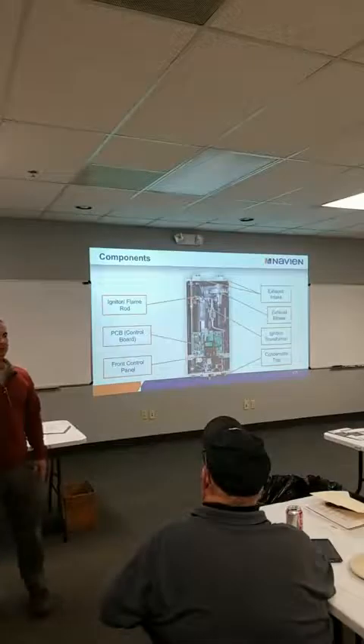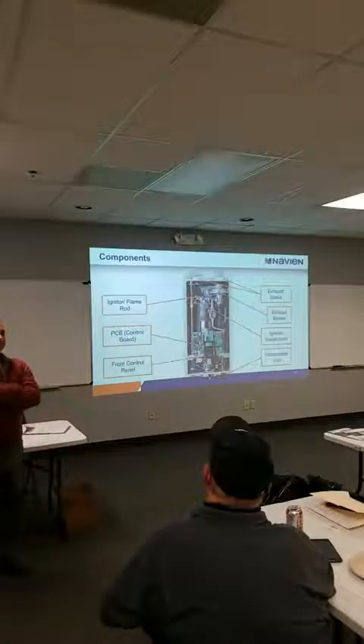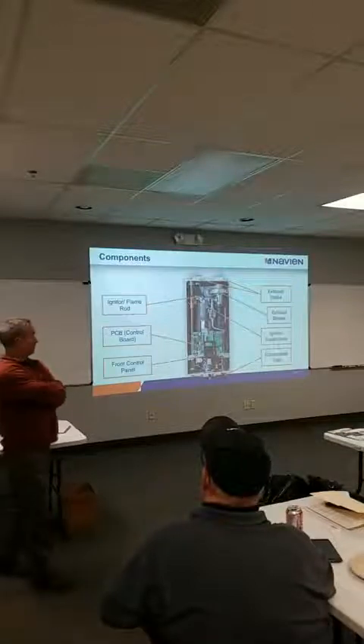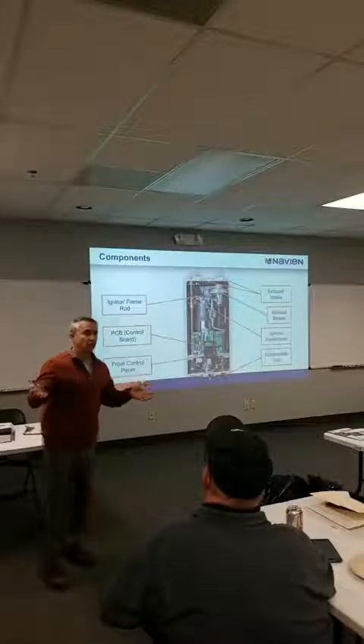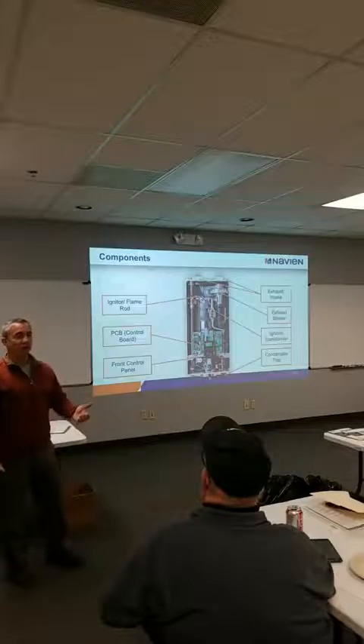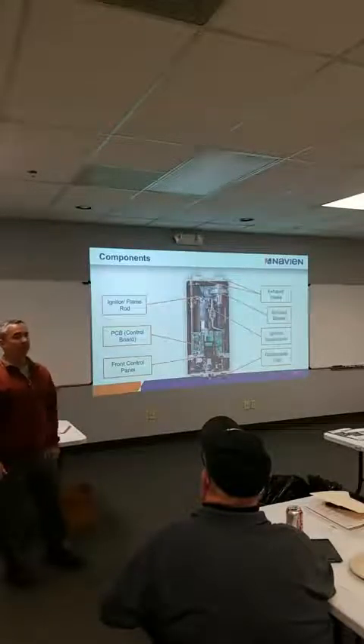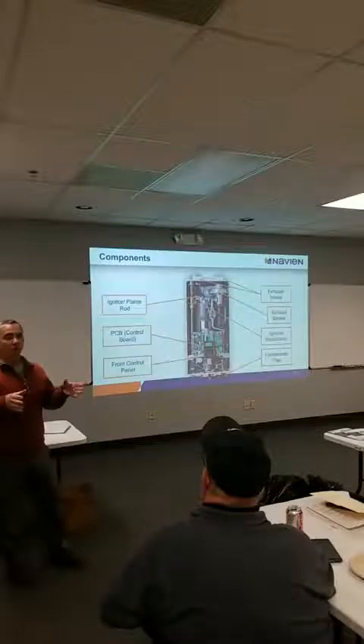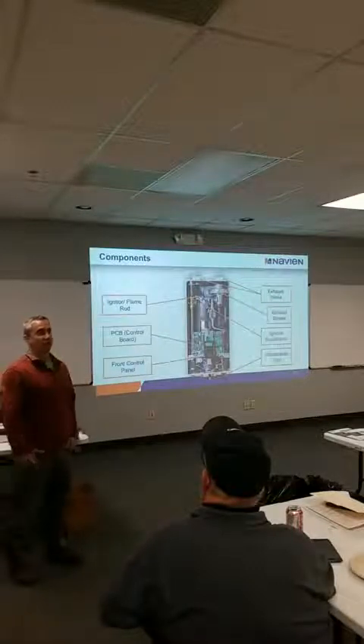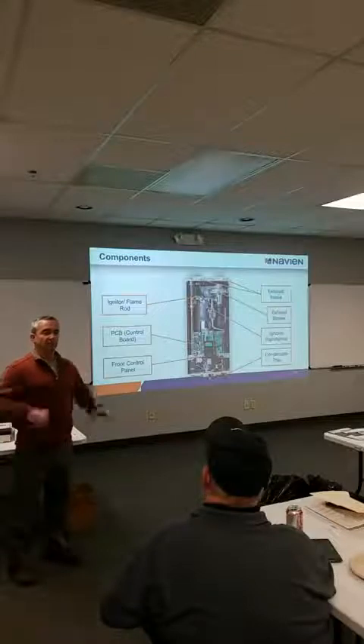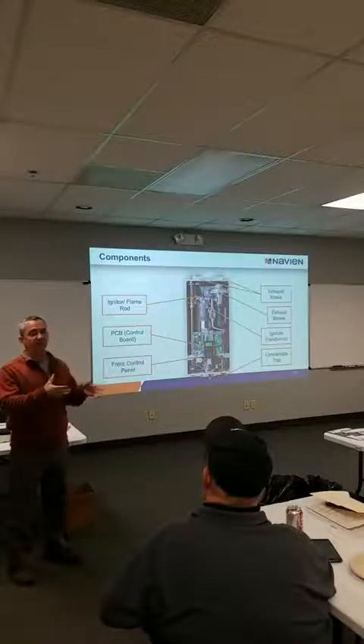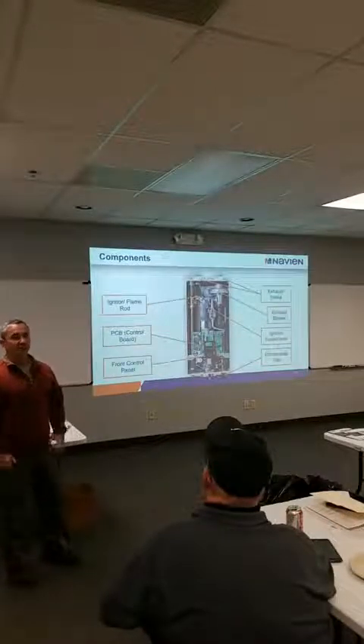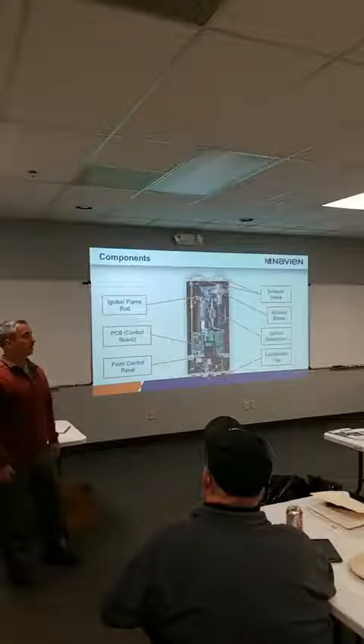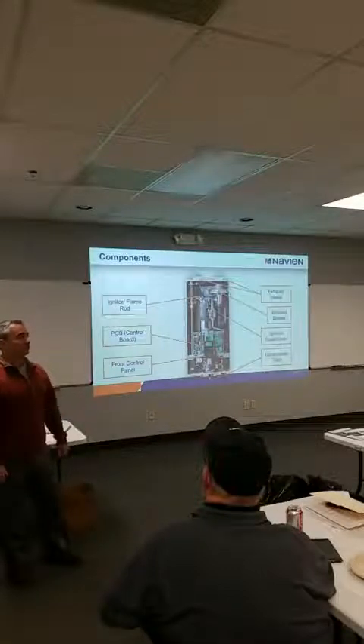The fire tube, because it's that big open vessel, we can get more primary out of it. Is the advantage of the fire tube over the water tube the fouling? Yeah, because it's just a bucket holding water, you got low head pressure, we can move a lot of water through that system, so we get more BTUs out, and we can keep that box small. The whole point is you can lift that thing up and hang it on a wall. We're trying to keep the box small, that's why we pulled the condensate trap out on the fire tube, because we'd have had to make more room for it inside, just easier to put it on the outside.